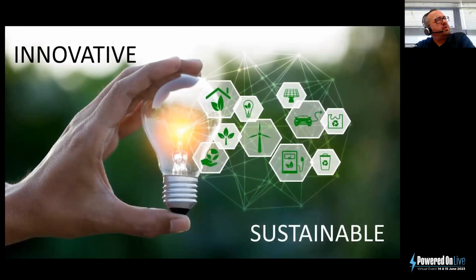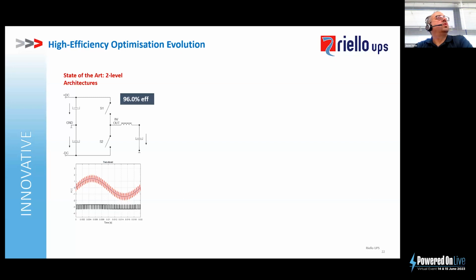So what I want to do now is look at how we got to this point in the marketplace. So let's look at where we went in terms of the innovation in UPS design. Well, many years ago, we used to produce what's referred to as a two-level architecture inverter. So effectively, UPS systems of this type would typically produce an efficiency level of around 96%. Now, don't get me wrong, that is a very good efficiency even by today's standards, but obviously it's not as advanced as we are now.